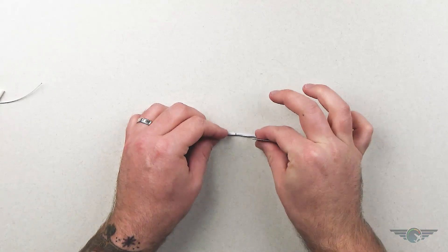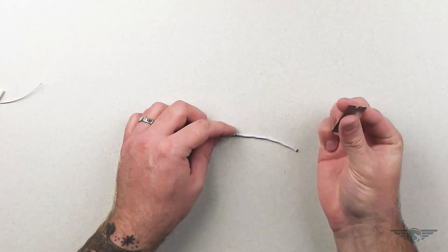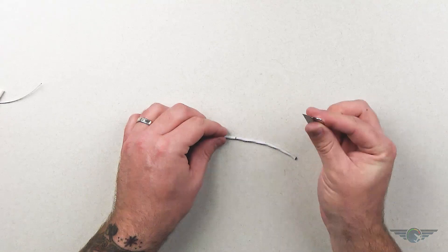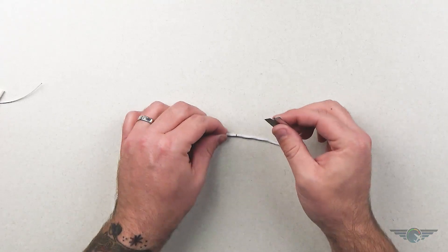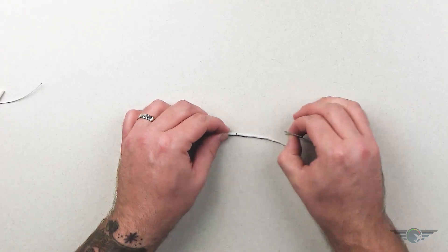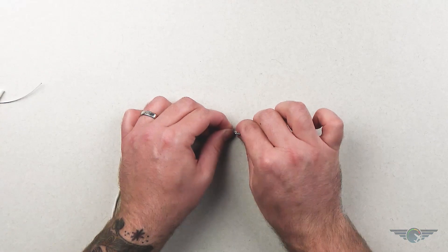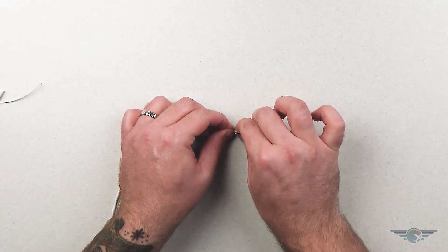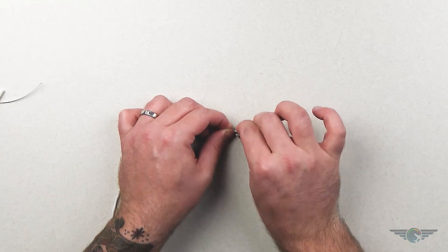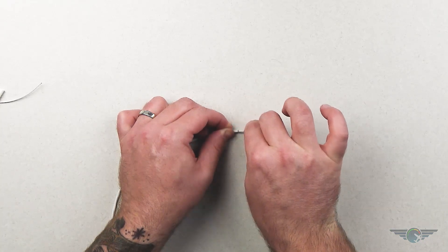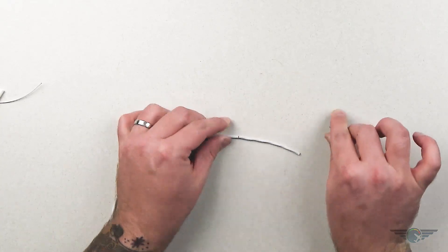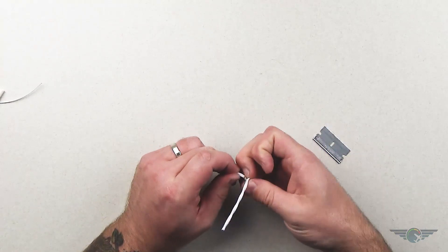Now I use my fingers and I touch my fingers on the table, and that way I can set the depth of my razor, and we don't want it to go very deep. We want to make sure our conductor doesn't get nicked or anything like that. We don't want to go through the shield. So I'm going to set my depth, and this also kind of guides you along the wire here. So there, got that.